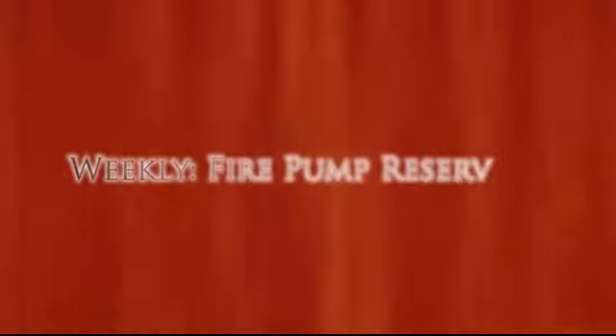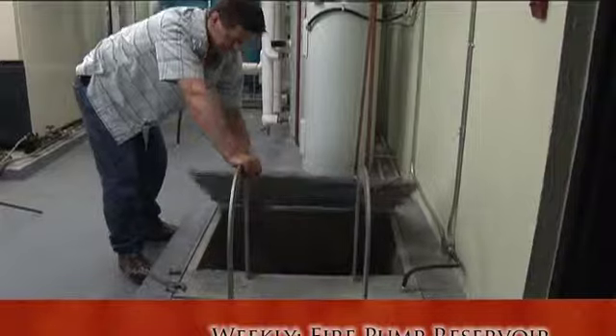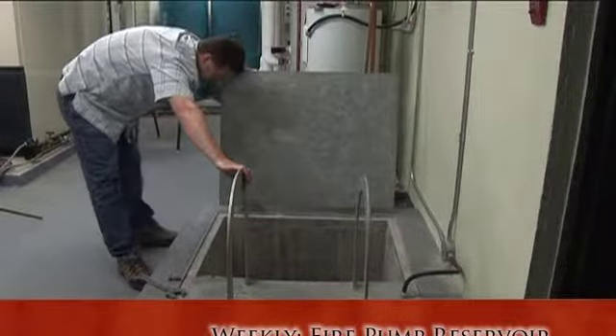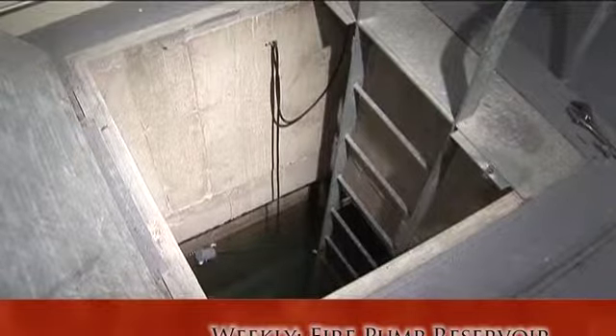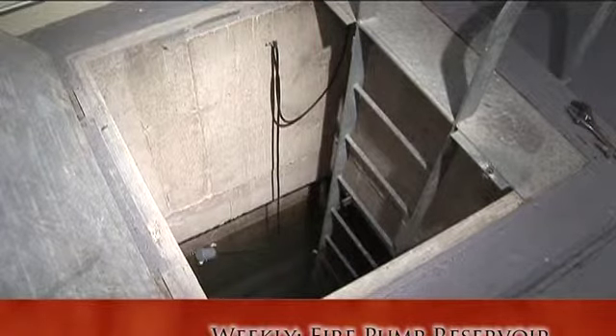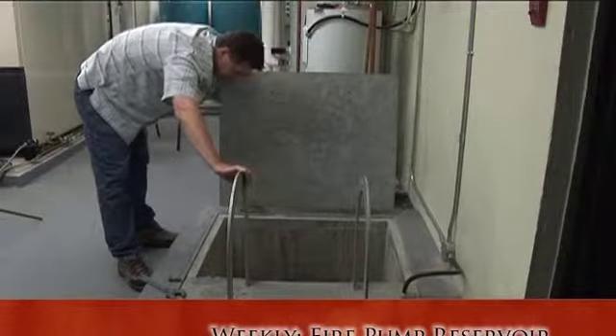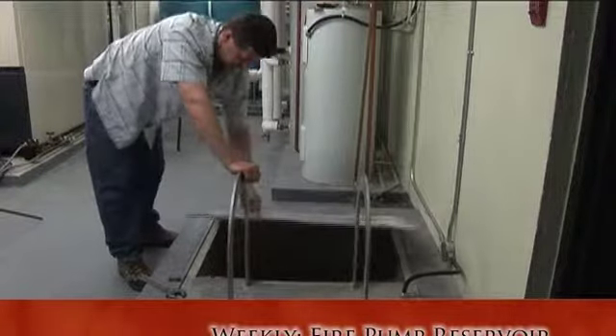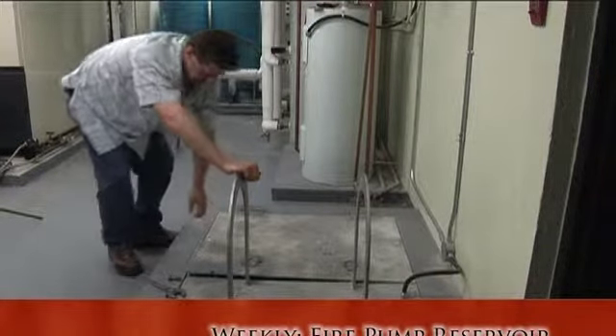The following items need to be inspected or tested on a weekly basis if your school has them. Fire water supply reservoirs need to be inspected weekly to make sure the water level in the reservoir is at or near the normal level. If the reservoir water level is notably lower than the normal level, contact your supervisor immediately and have technical personnel assess the problem. Note that these levels may be monitored and adjusted electronically.